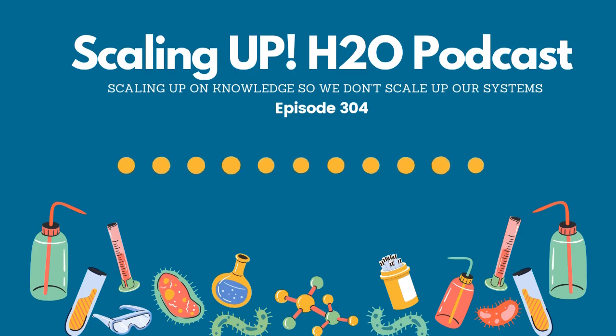Where I really like to use that is where we can do something with it. So maybe we're trying a new inhibitor, or maybe we're trying a new biocide, and every time that feeds, we can now get real-time data on what happens on that metal tip based on that feed. So I love to use those for that. And then we have customers that have very specific pieces of equipment and they want to know all that data. But I'm going to tell you a secret. I run corrosion coupons even if I have those Corrators, and again, that's the name brand, I can't think of the other thing, in the system, because that allows me to utilize both sets of data to get more information about the system.